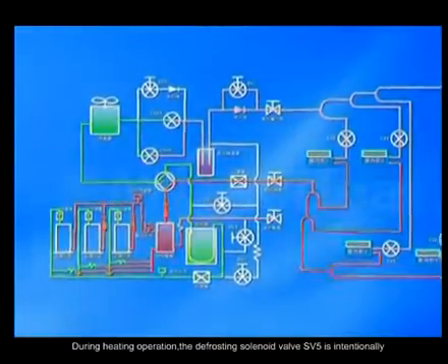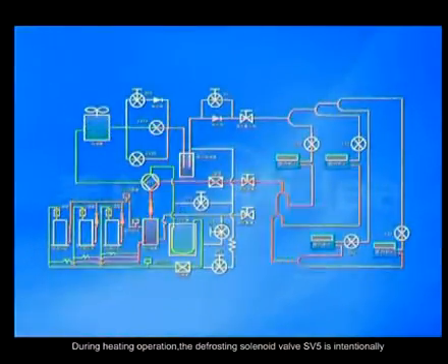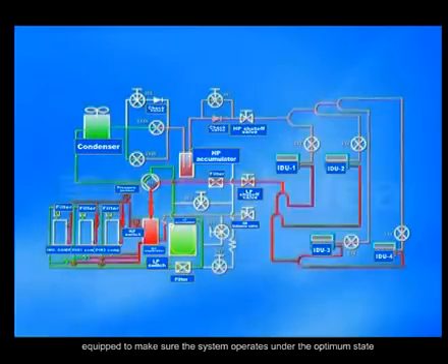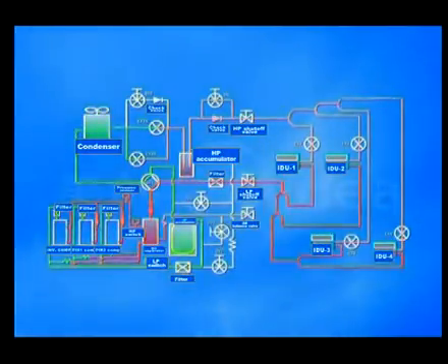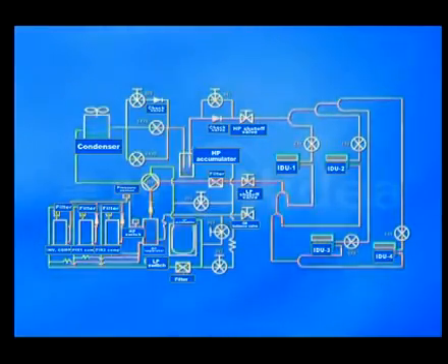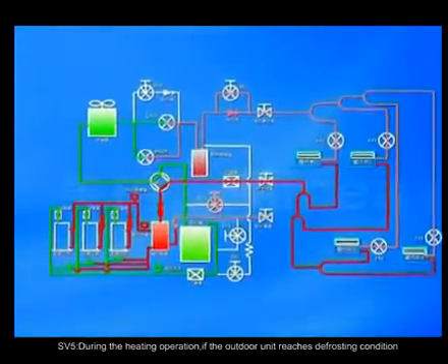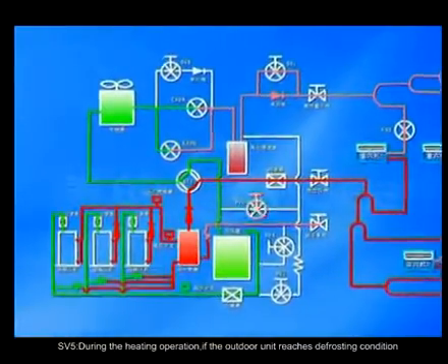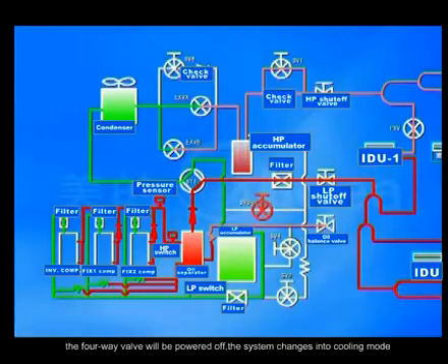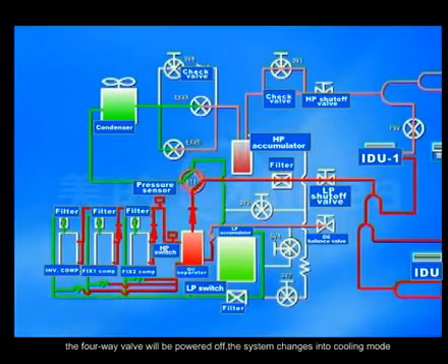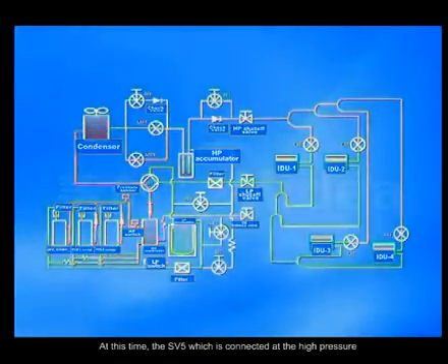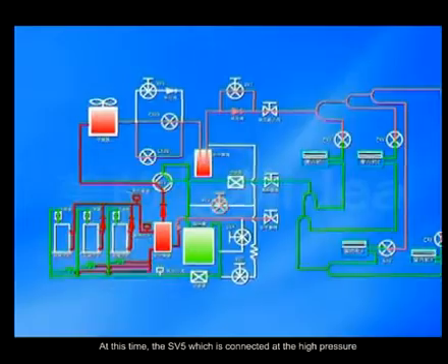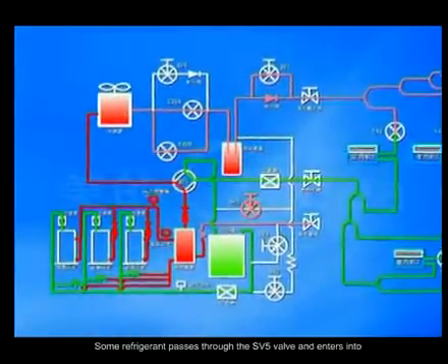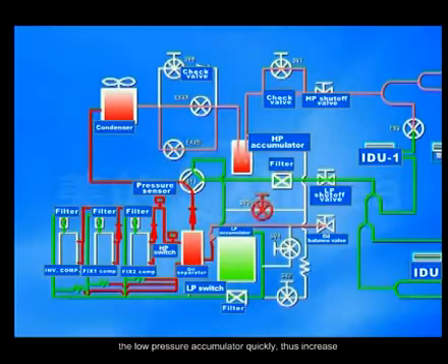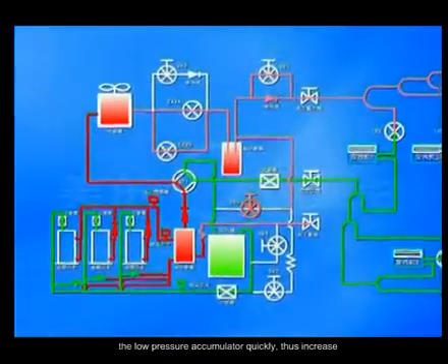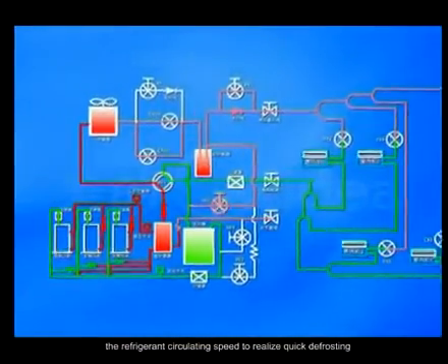During heating operation, the defrosting solenoid valve SV5 is intentionally equipped to make sure the system operates under the optimum state. SV5. During the heating operation, if the outdoor unit reaches defrosting condition, the four-way valve will be powered off. The system changes into cooling mode. At this time, the SV5, which is connected at the high-pressure accumulator outlet, will be powered on. Some refrigerant passes through the SV5 valve and enters the low-pressure accumulator quickly. Thus, it increases the refrigerant circulating speed to realize quick defrosting.